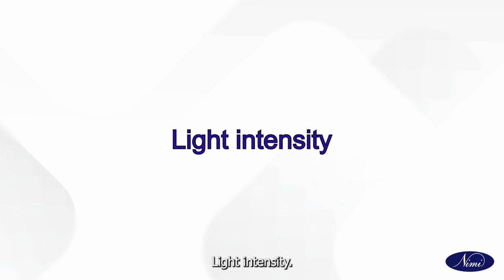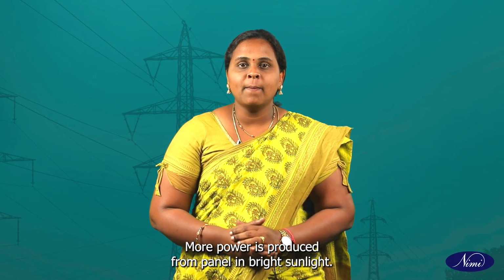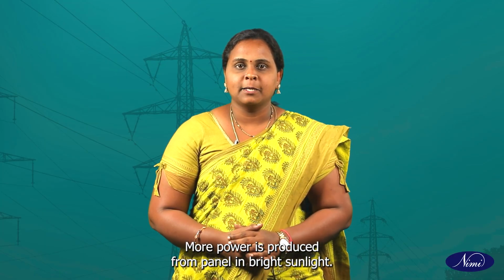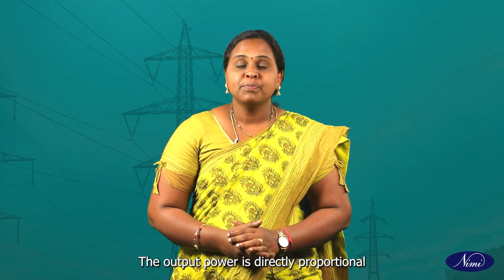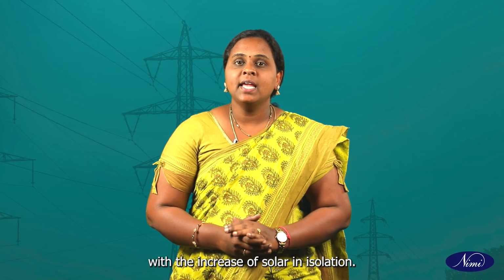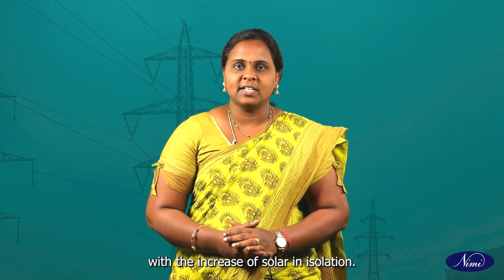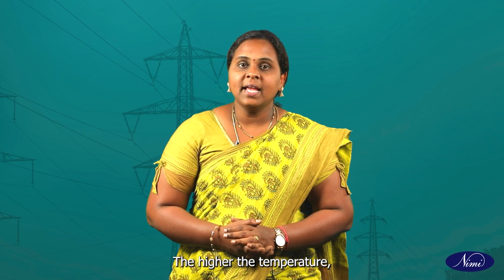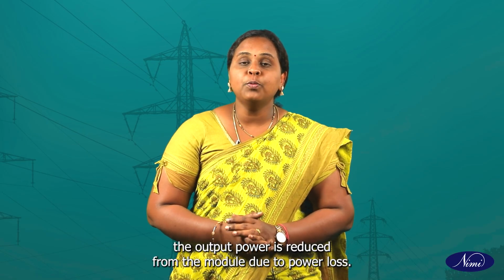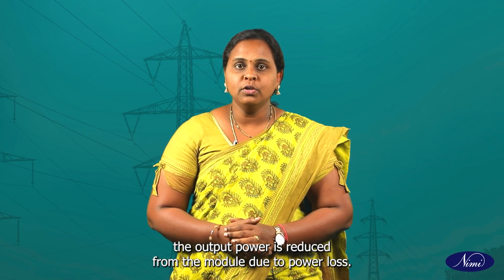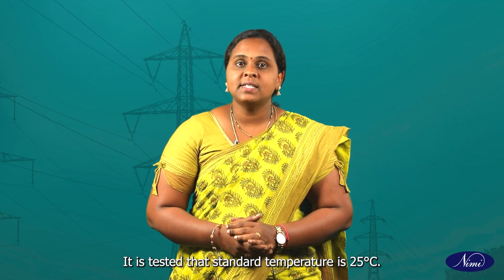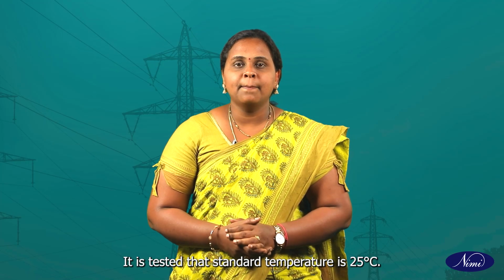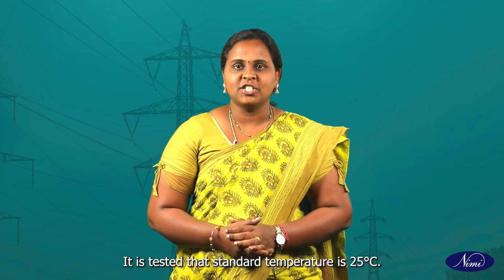Light intensity. More power is produced from the panel in bright sunlight. The output power is directly proportional to the increase of solar insolation. Temperature. The higher the temperature, the more the output power is reduced from the module due to power loss. It is tested that the standard temperature is 25 degrees Celsius.